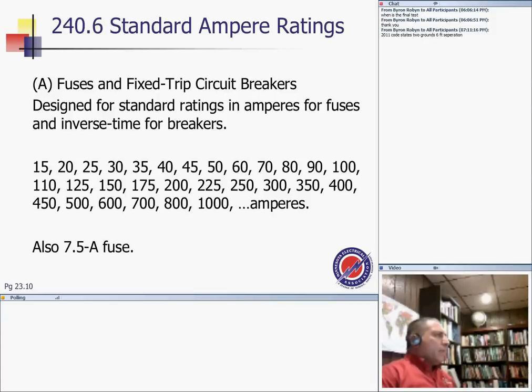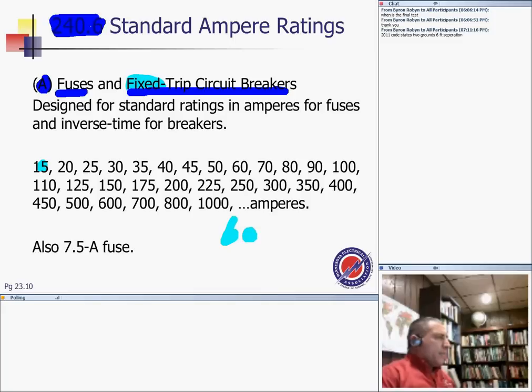This is one of the single most important things, guys, that you should know about fuses. These are fuses and fixed. I can't emphasize the word fixed enough. If you deal with adjustable circuit breakers, guys, that does not apply to them. It can go from 15 all the way to 6,000 amps from this table. The most common, largest that I've seen is 4,000 amps. 4,000 amps switchgear with an overcurrent protection device, 4,000 amps.